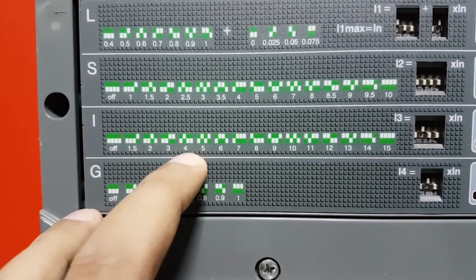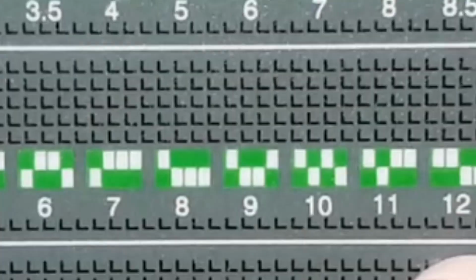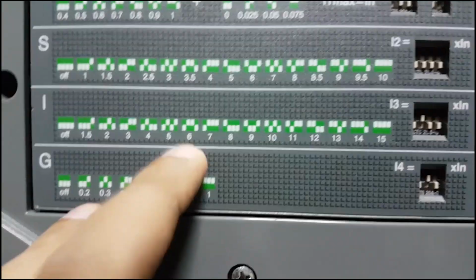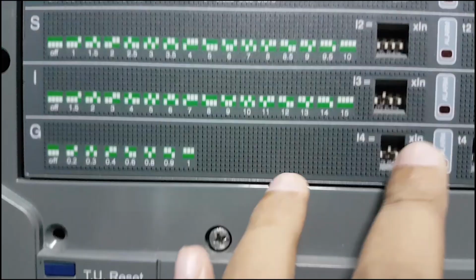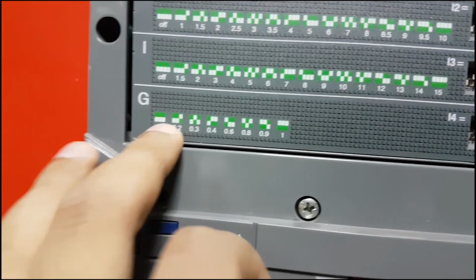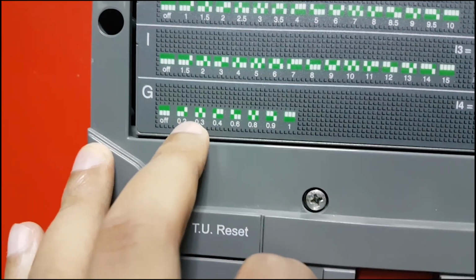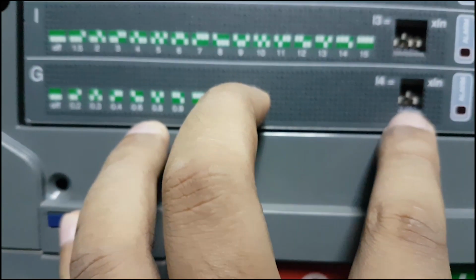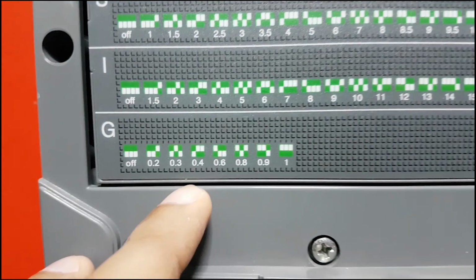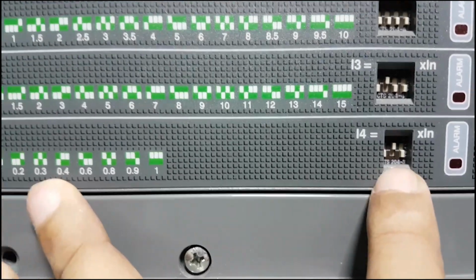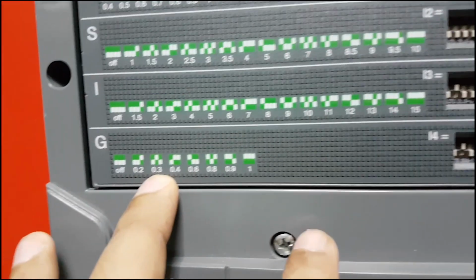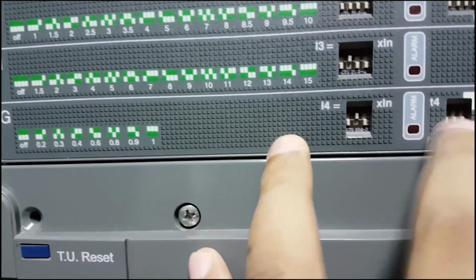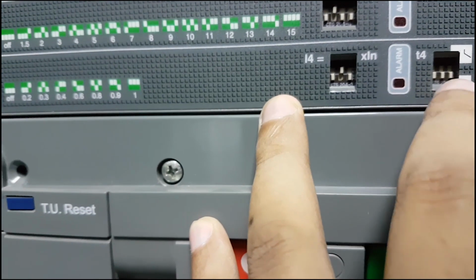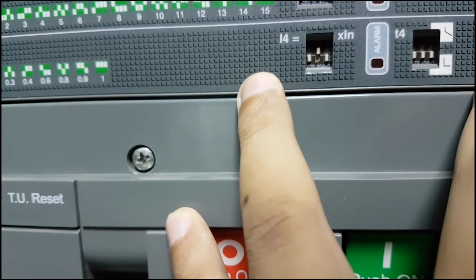For instantaneous current, here it is set to 4, so 4 times In. It's 4 times In, and it means 8000 ampere. And for this there is no time. And this G is ground fault. Here it's showing 0.3. Look at this, 0.3 of nominal current, and time is 0.1.